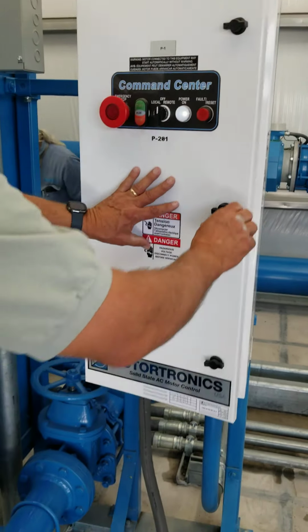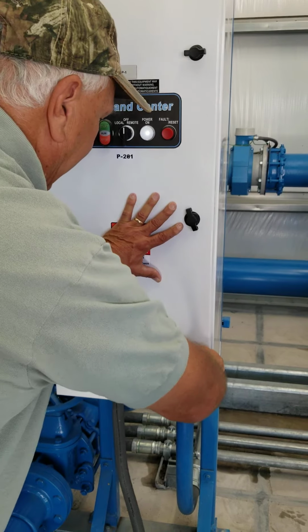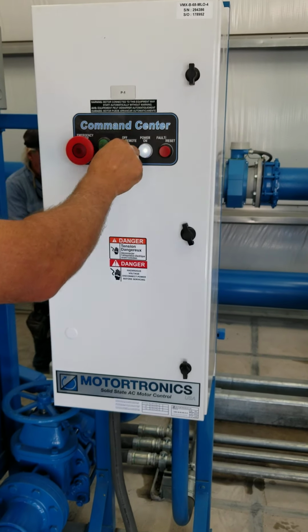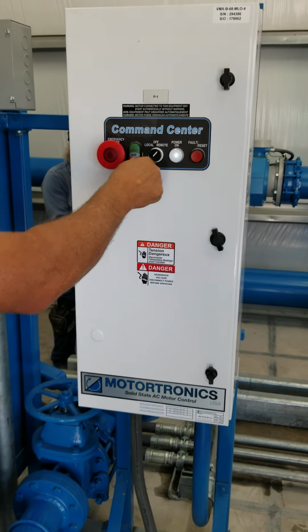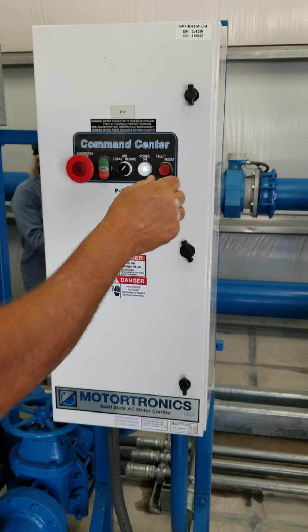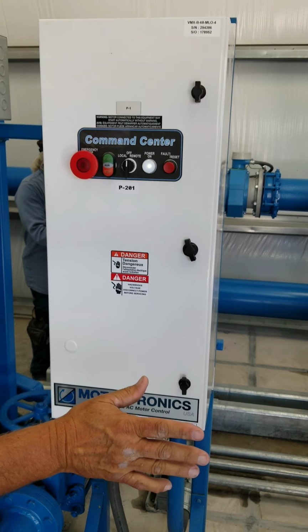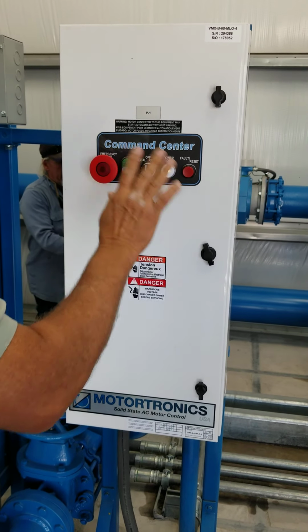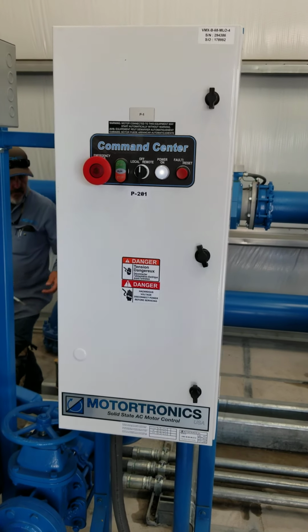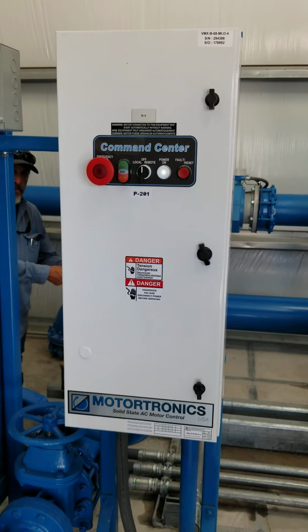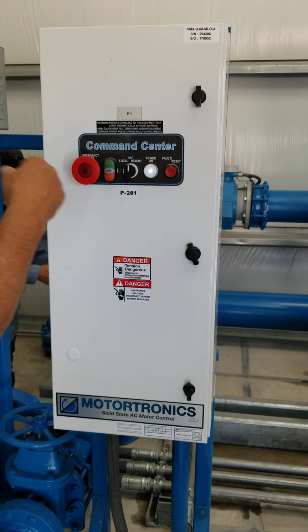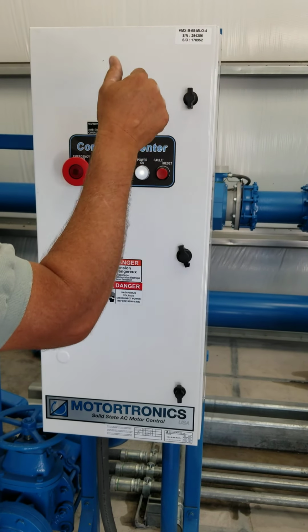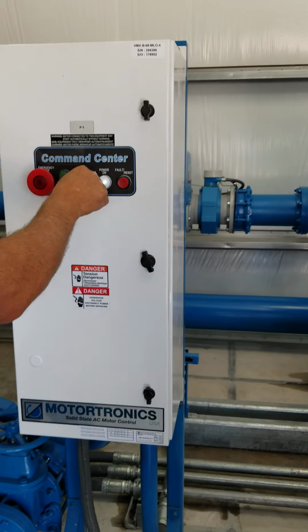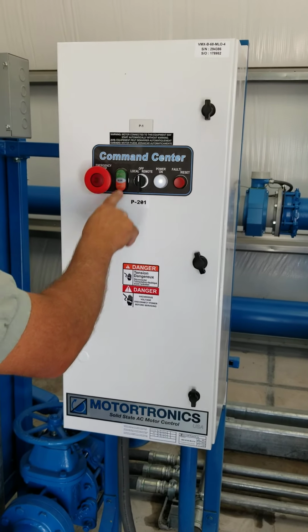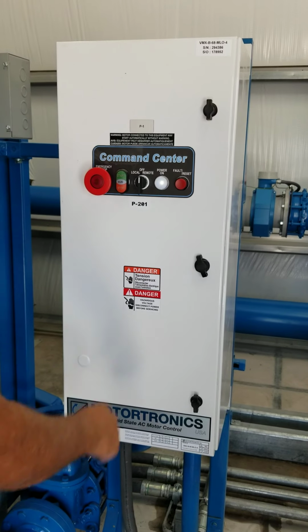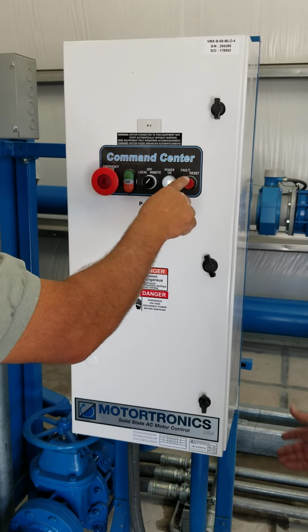But what we did is, it didn't come like this, but we added a different HOA. So now when we put it in remote, it shows up over there. And when you take it off, it says it's not in auto. I don't really like this hand button because these pumps generate 360 feet of pressure, so I don't really like running them in hand. Anyway, they're in remote, and if you ever need to, you've got hand. I think you probably have to hit that start button. They moved it off the side and put it on the front.